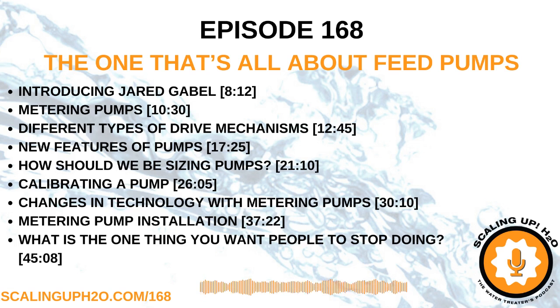So this is going to be more on the electronic side. And a lot of times the pumps will have some kind of a warning that says something to the effect that maybe the motor is not working correctly, or if you're noticing that it's just pumping without a signal, for example, just the weird stuff. Like, let's say you have a 4 to 20 milliamp signal coming in, and it's not reacting to that for some reason. There could be something on the PCB side of things that nobody in the field is going to be able to know what to do.